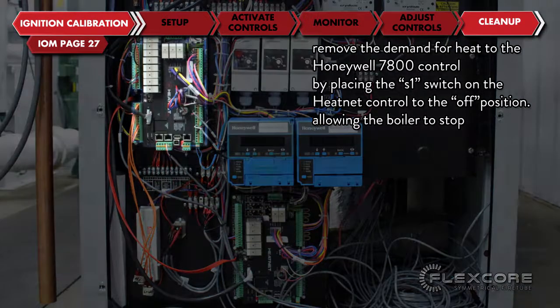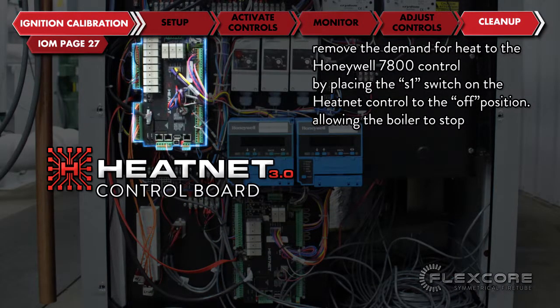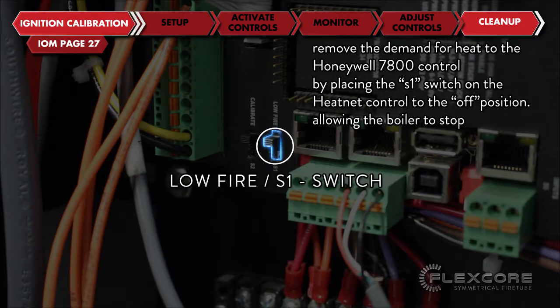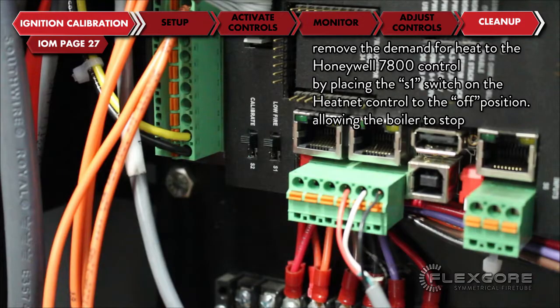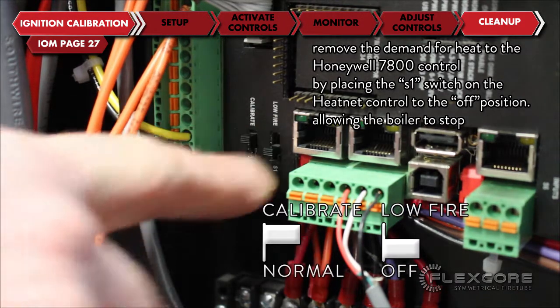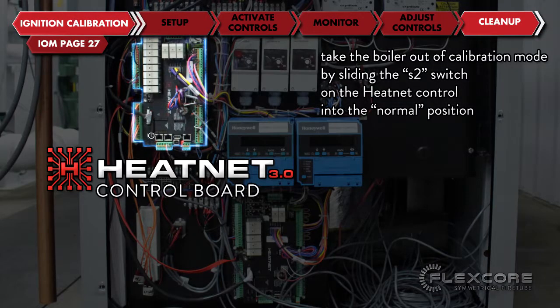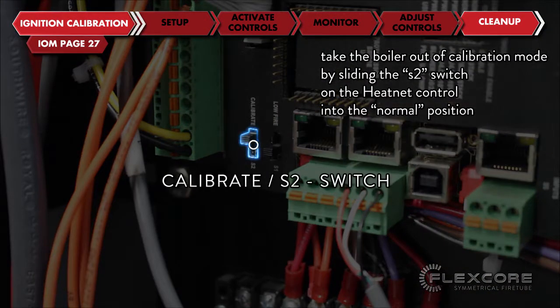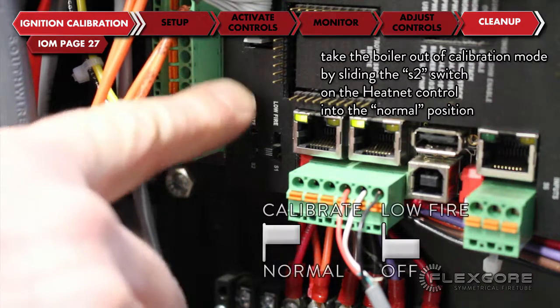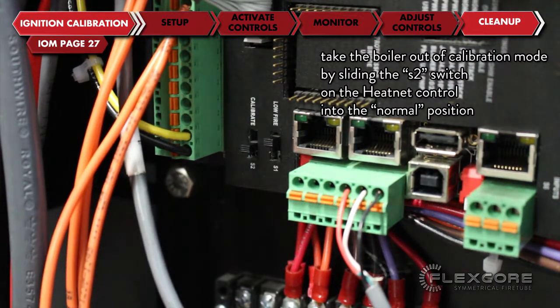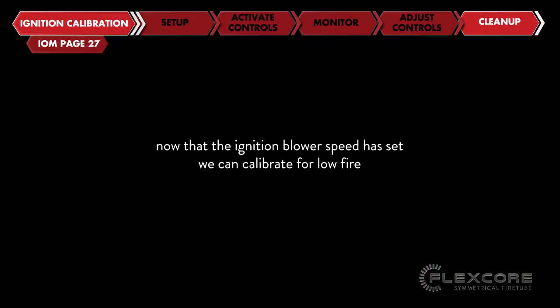Then, remove the demand for heat to the Honeywell 7800 control by placing the S1 switch on the heatnet control to the off position, allowing the boiler to stop. Take the boiler out of calibration mode by sliding the S2 switch on the heatnet control into the normal position. Now that the ignition blower speed has been set, we can calibrate for low fire.